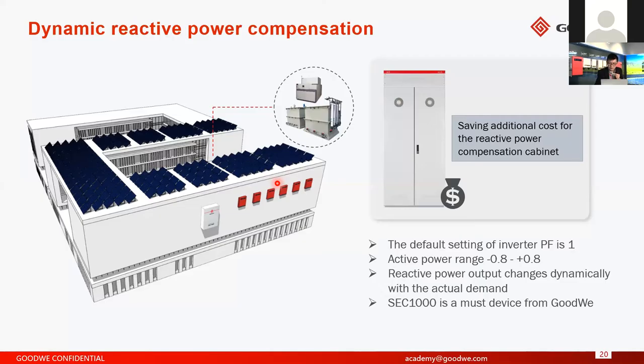So for our product, you can set the PF value in the display or even in our app. For the active power, the PF range is from minus 0.8 to positive 0.8, which means the reactive power range will be from minus 0.6 to positive 0.6. And also it's dynamic, not static. The inverter's reactive power output will be the same as the load's consumption. So you don't need to set the PF value manually. If you use our SEC 1000 box, this box will adjust the PF value automatically.